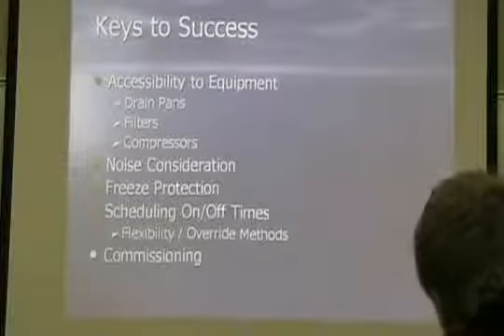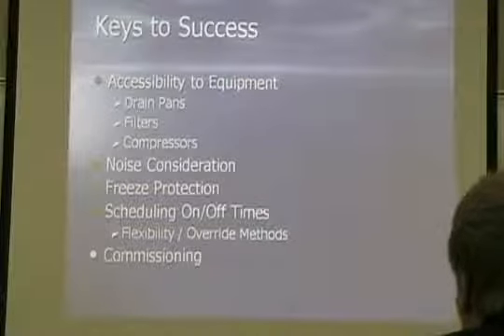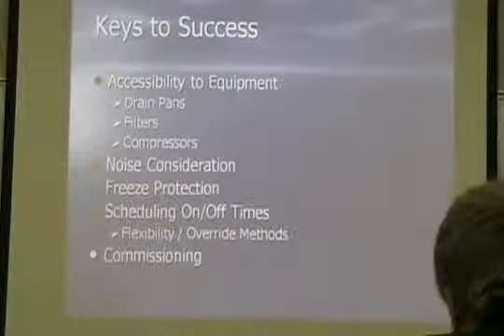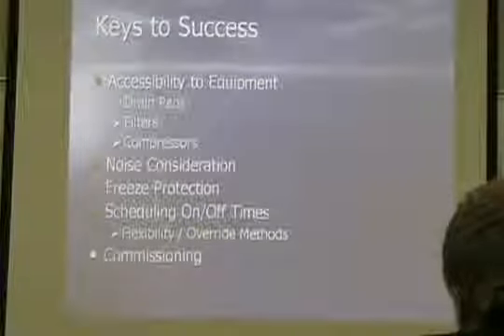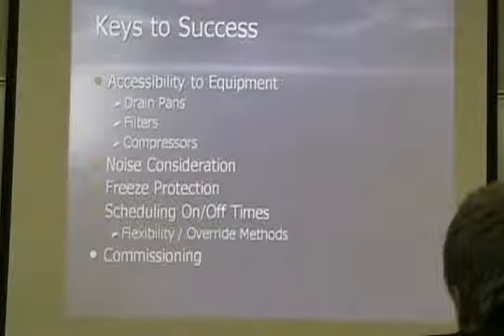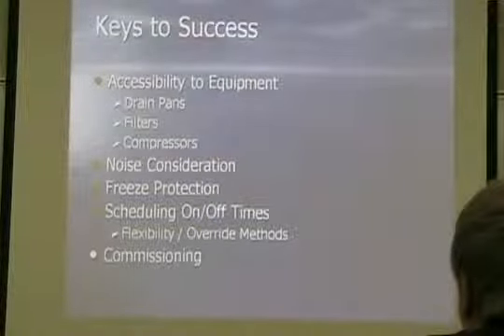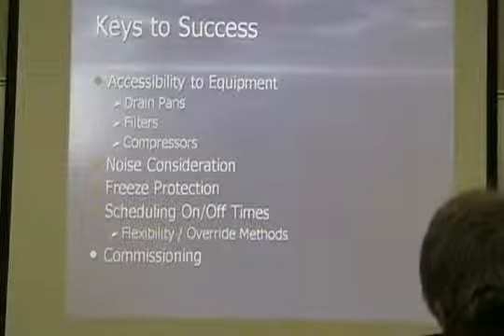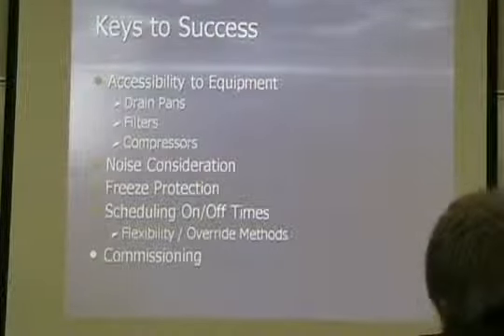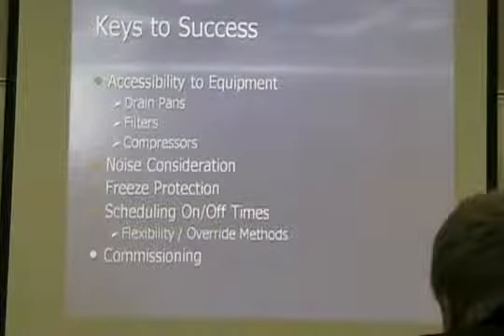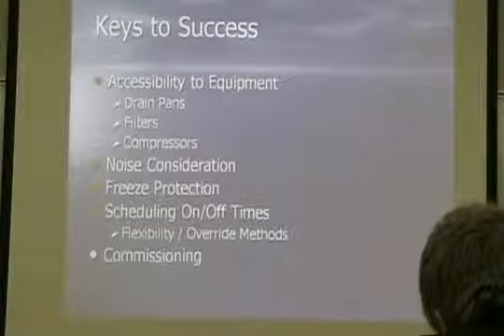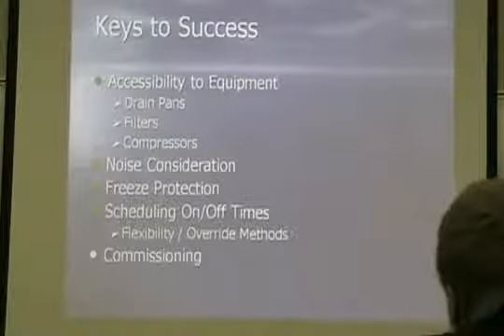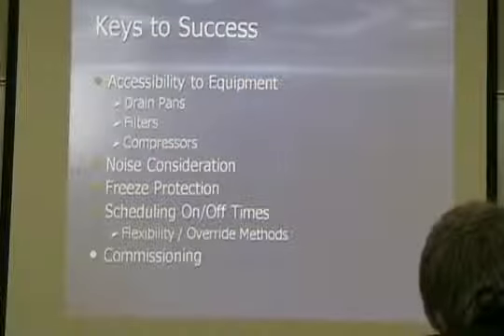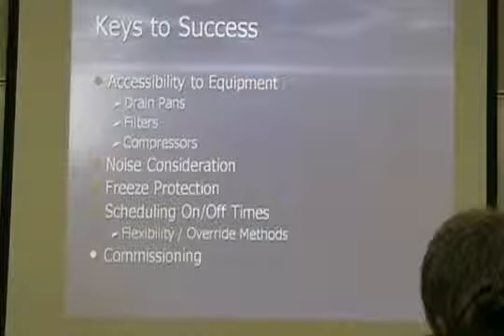Accessibility to the equipment, drain pans, filters, and compressors. You have one access door on the front of the unit that gets you to everything, versus climbing in an air handling unit. Noise considerations: generally you can get compressor blankets on water source heat pumps to reduce compressor noise. Most manufacturers are putting these little scroll compressors and recip compressors in these units nowadays, and they just don't make noise. So you don't generally have the problems you might have had 10 or 15 years ago with horizontal units above the ceiling, where you had to consider noise.